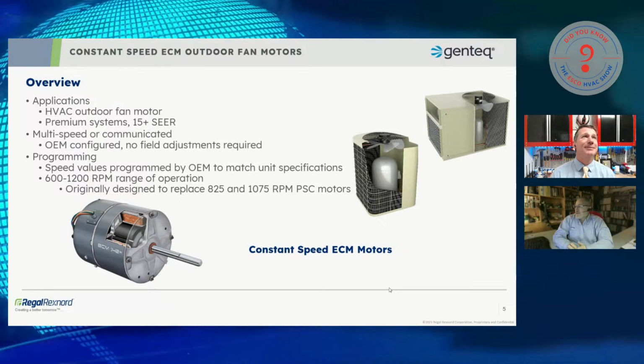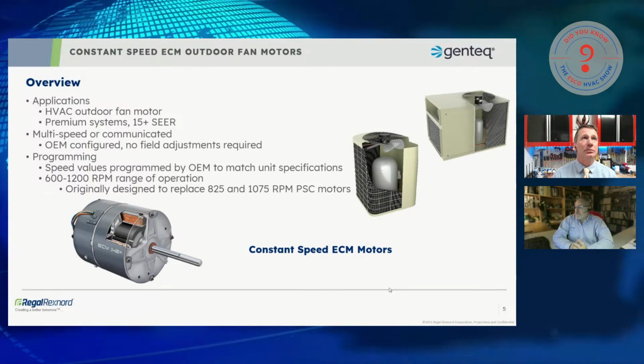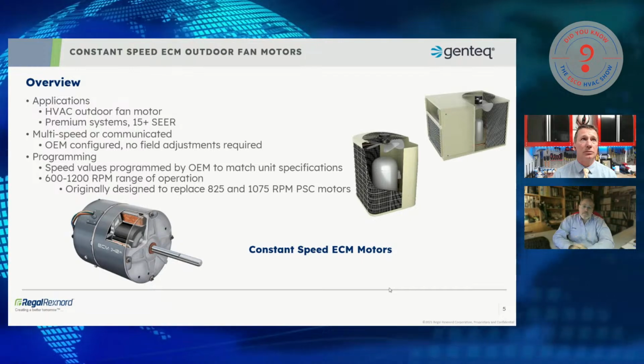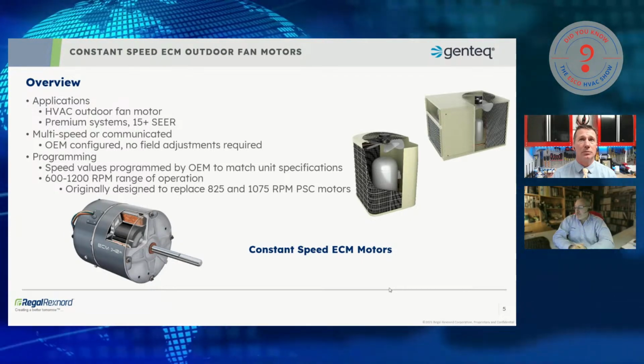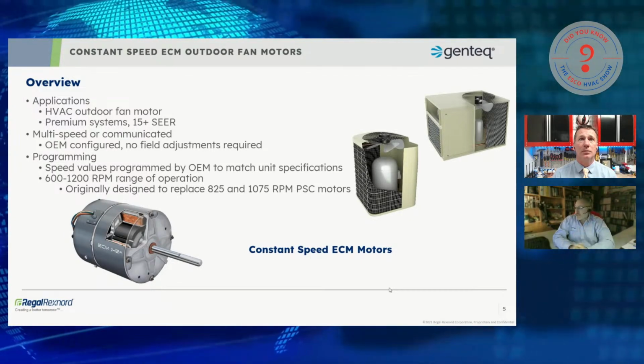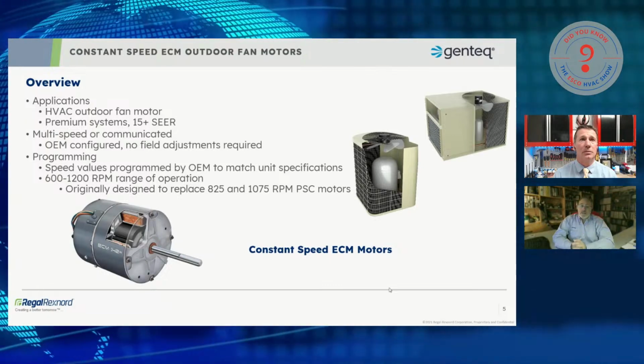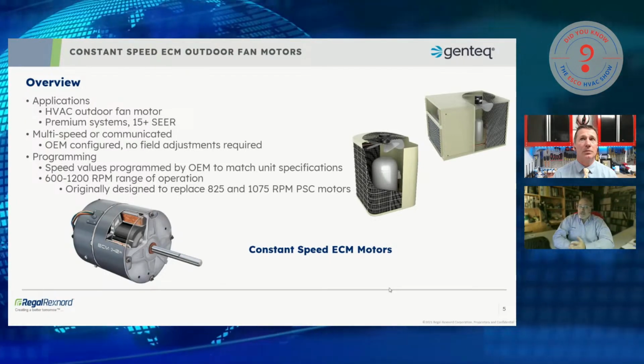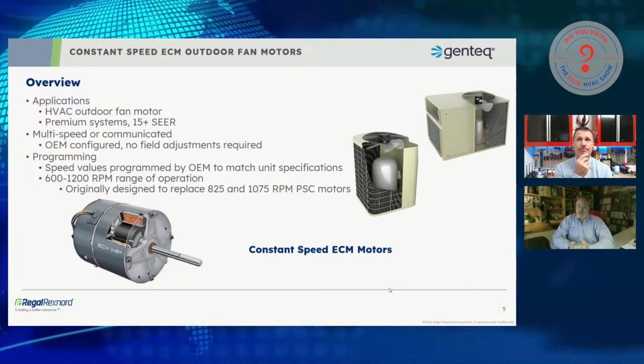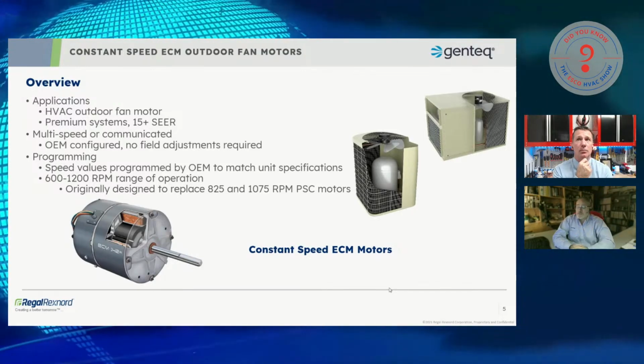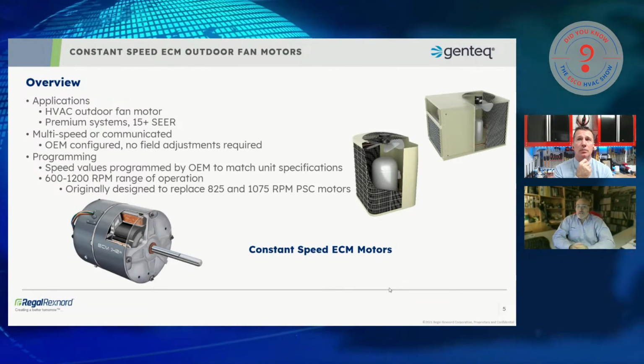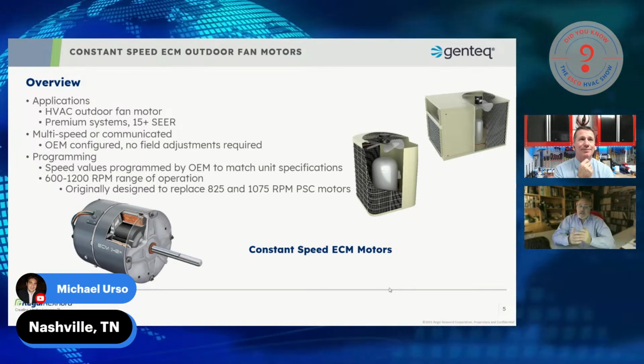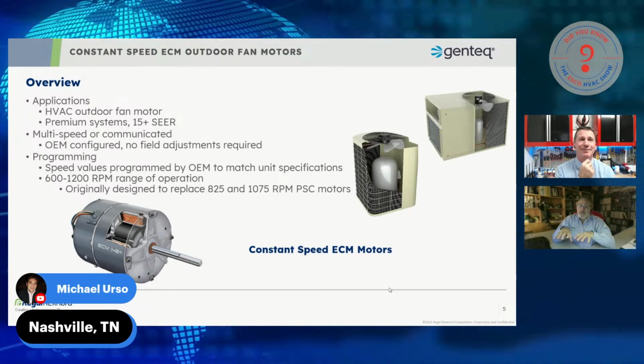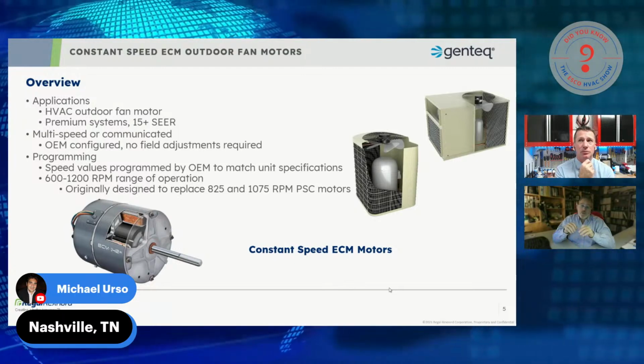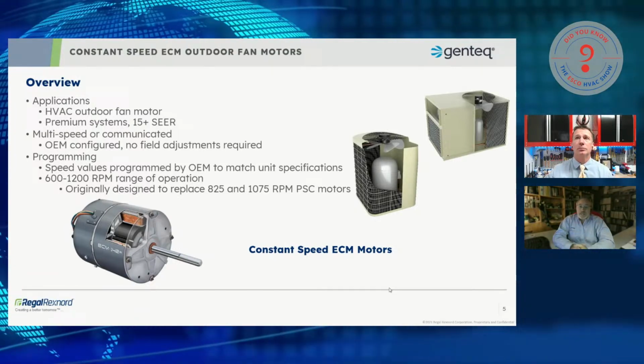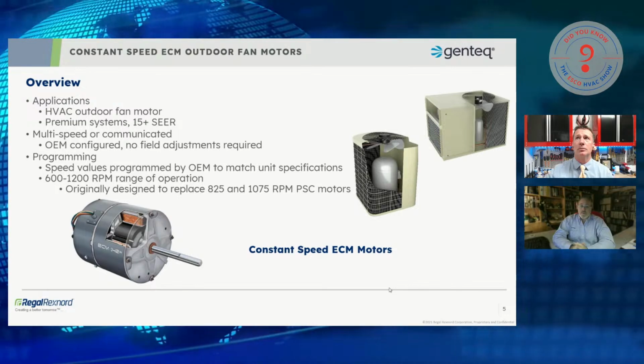There you go. So again, just a little bit of an overview. These motors are found in residential and light commercial, 5-ton or less HVAC applications, typically 15 or 16 SEER and above. Now, these motors could be either multi-speed or communicated, and we will dig a little deeper into both of those so you understand what we mean by multi-speed or communicated. And they are, like all other ECMs, OEM configured, meaning they are programmed by the manufacturer to operate at the speed or speeds that the manufacturer needs for their single or two-stage equipment.